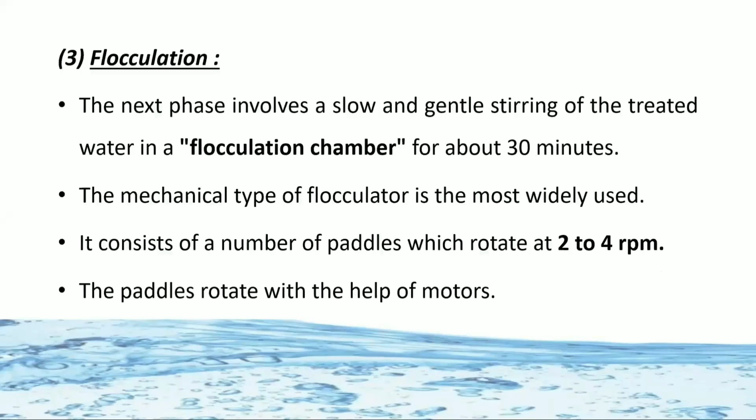After rapid mixing, there is flocculation, means slow and gentle stirring of the water. There is a flocculator, which is a mechanical flocculator that rotates with the help of motors, and it rotates at the rate of 2 to 4 rpm.